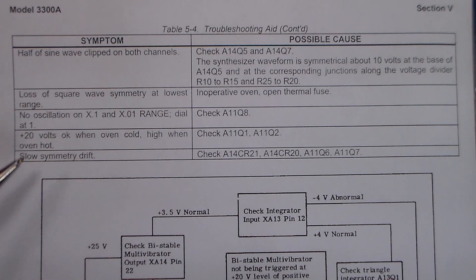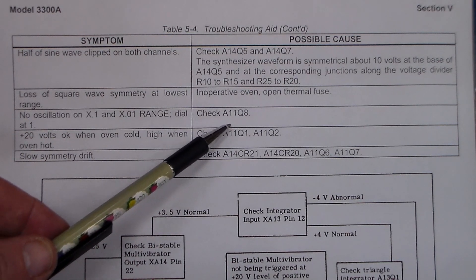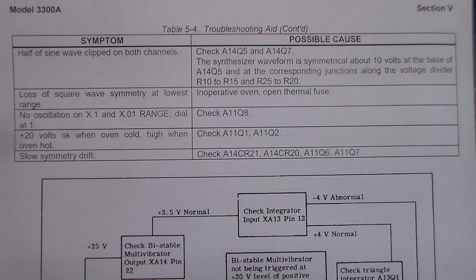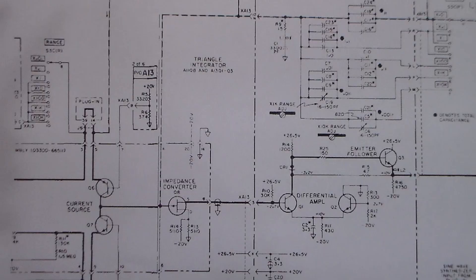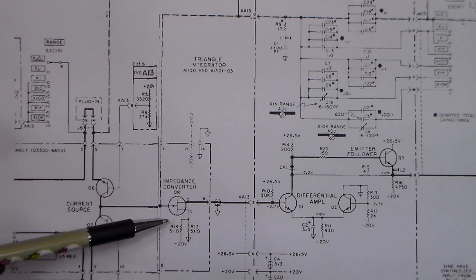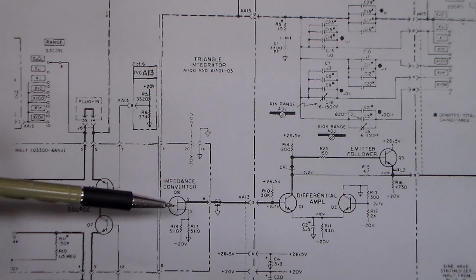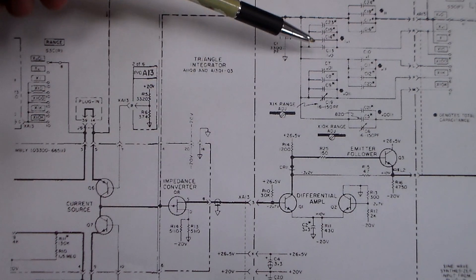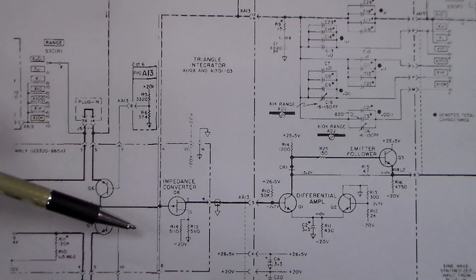The manual says to check A11 Q8. The A11 board is in the oven, and Q8 is a p-channel FET used as an impedance converter. Going to the schematic, Q8 is shown here as part of the integration assembly, even though Q8 is actually located in the oven.